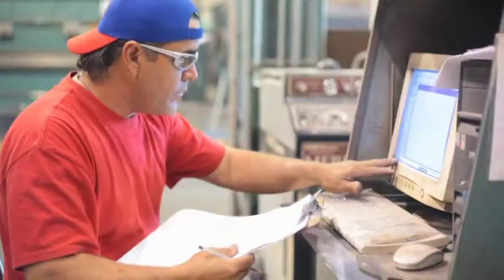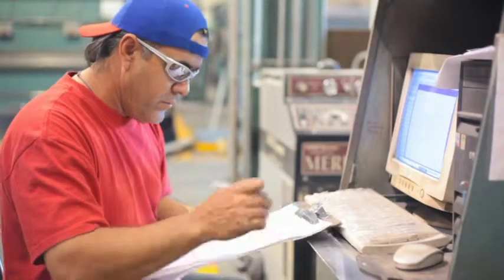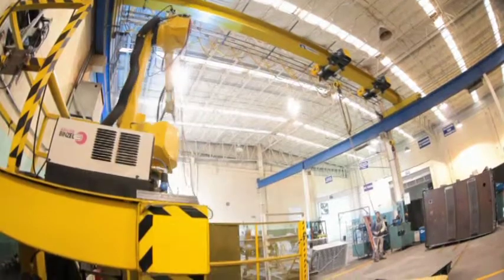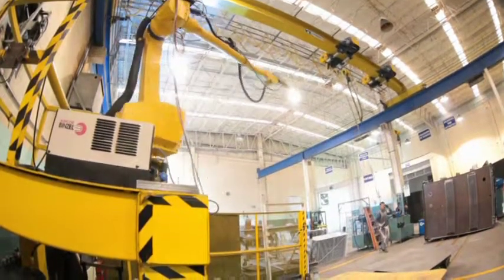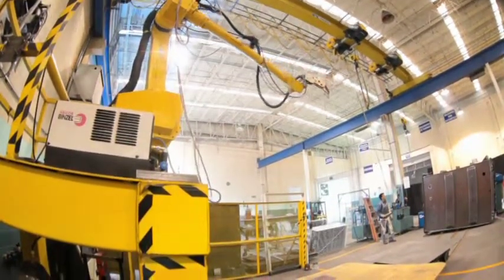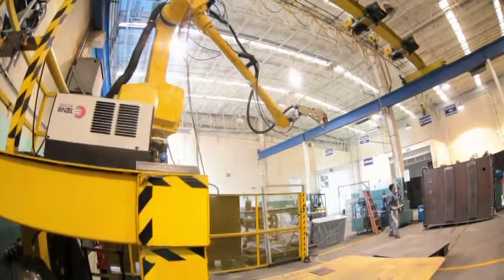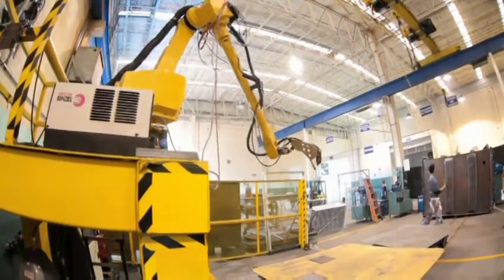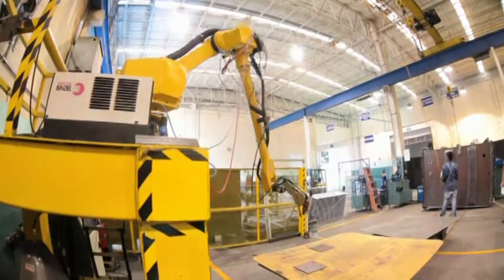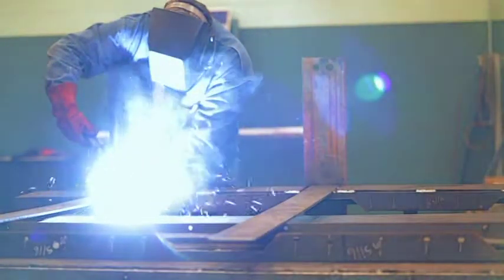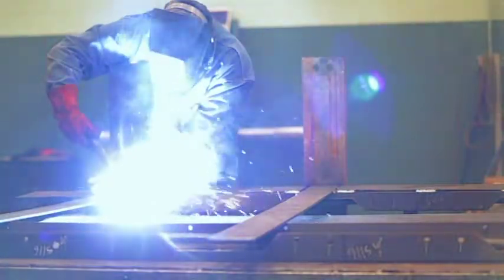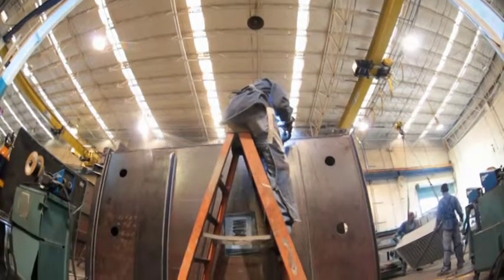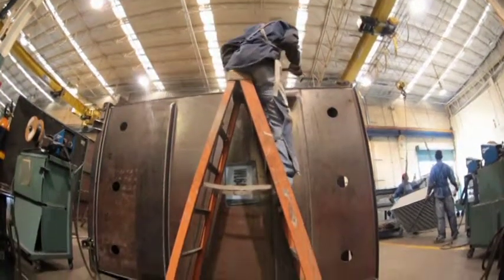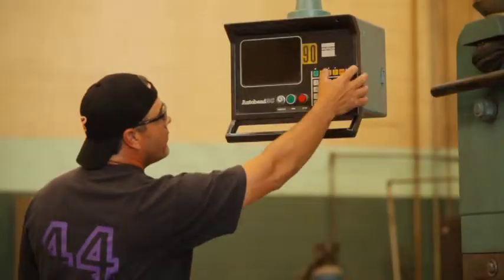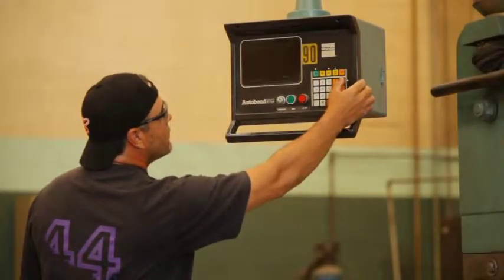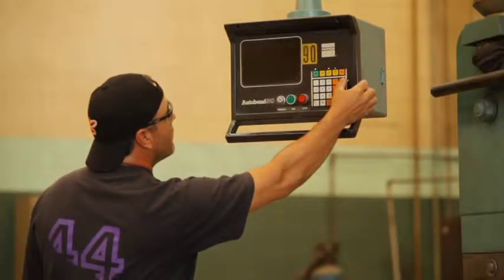At the inspection process for the tank manufacturing, it is verified that the tank meets all critical and important measures, inside and outside, set previously in mechanical drawings. Also, it checks all welds used to put all the pieces together that make up the tank. It is important to mention that all of our welders are certified, as well as all the welding processes used to ensure that the tank supports electromechanical forces. After finishing the whole welding process, the staff makes an initial pressure test to the tank to check for air leaks.